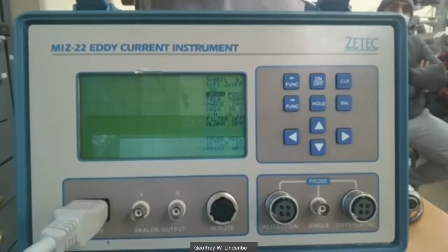Once we have our probe, I'll show you on the screen how we can move where that home position is using the up, down, left, right arrows. I'll make it bigger so you can see the probe display. While I was changing settings it went to 500 megahertz, or 500 hertz, hard to tell from my angle. I'm going to go back and move this to one of the default settings to clear it out.